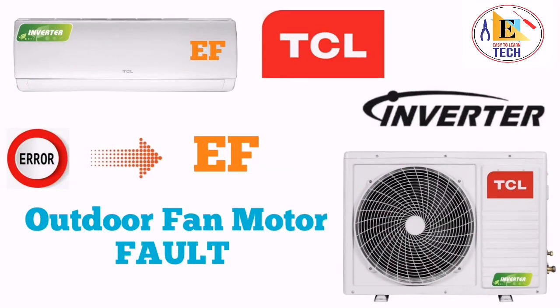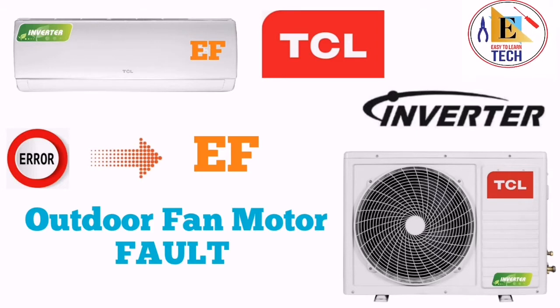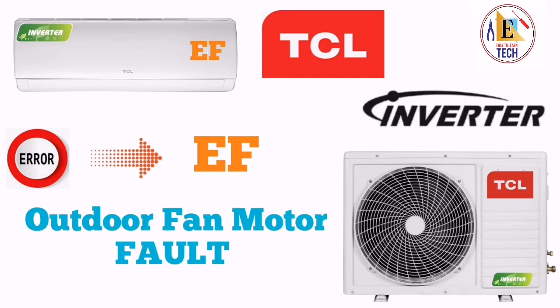When you see error EF, it means outdoor fan motor faulty. First of all, you have to check the connection of your fan motor, if it is connected properly to the PCB or not. If it is not connected properly, connect it properly and start the unit. And again, if it's showing the same error, then you have to check the resistance of your outdoor fan motor. And if your fan motor resistance is not good, then it means your fan motor is faulty. You have to replace the fan motor.